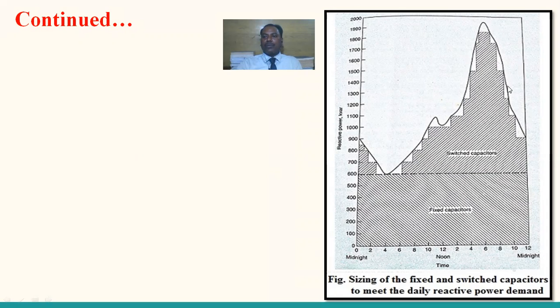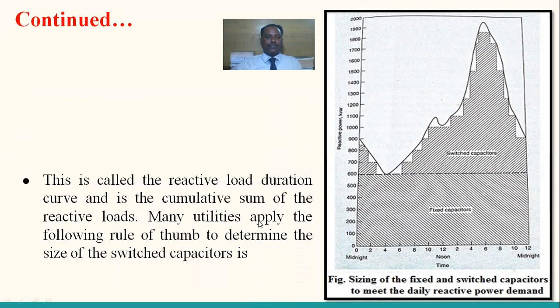where the maximum load is required. At that time, the maximum capacitor banks are to be switched on. When the load is reduced, the capacitor banks are to be switched off. So this figure represents the sizing of the fixed and switched capacitors to meet the daily reactive power demand.